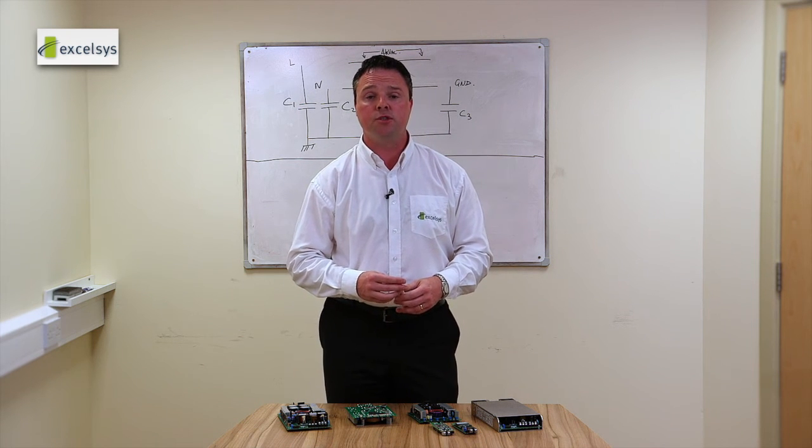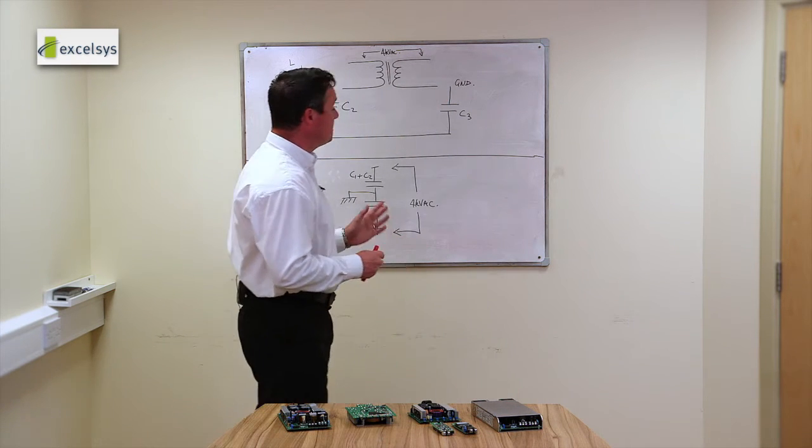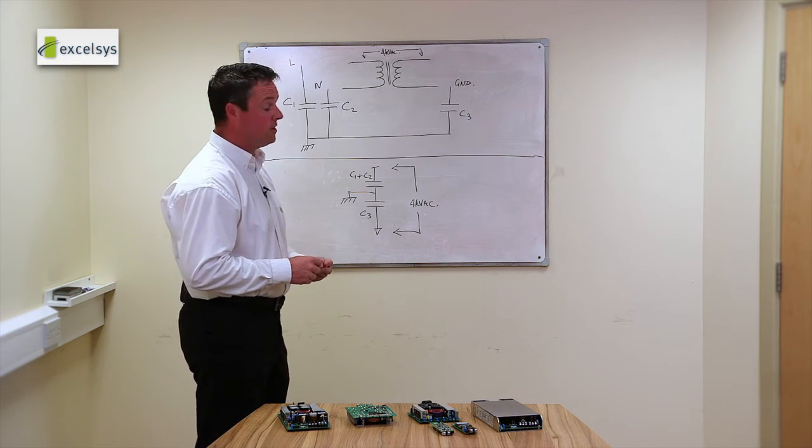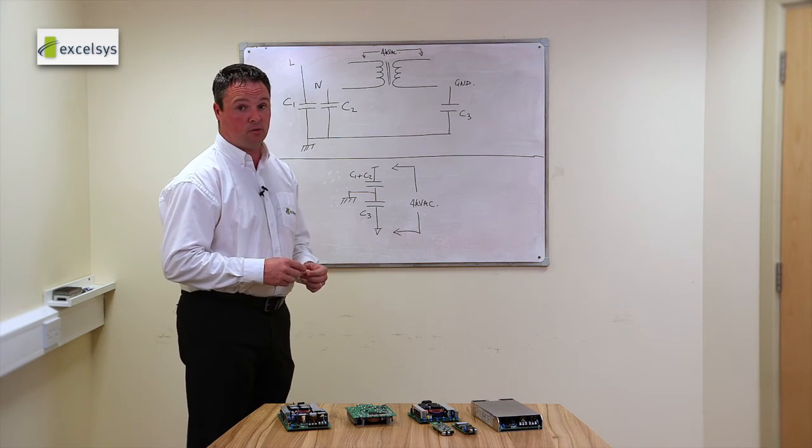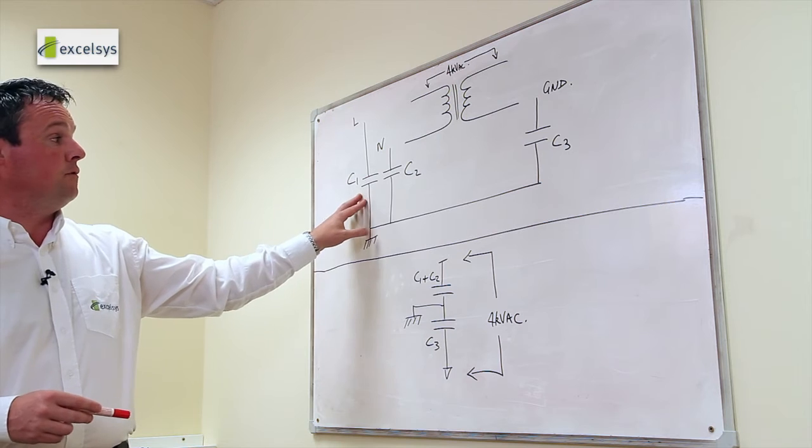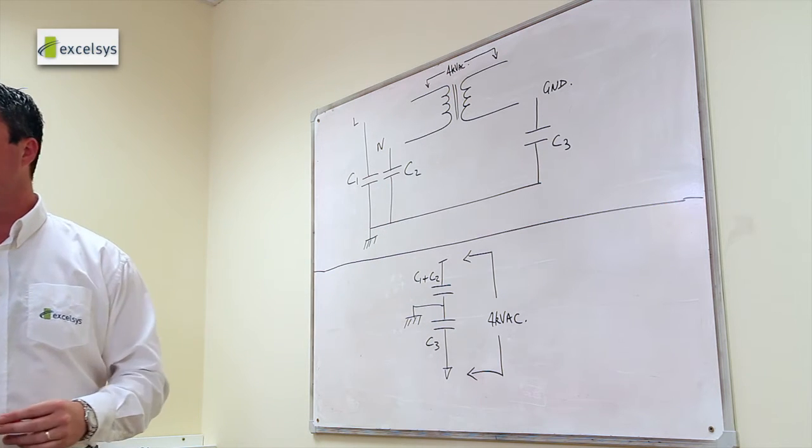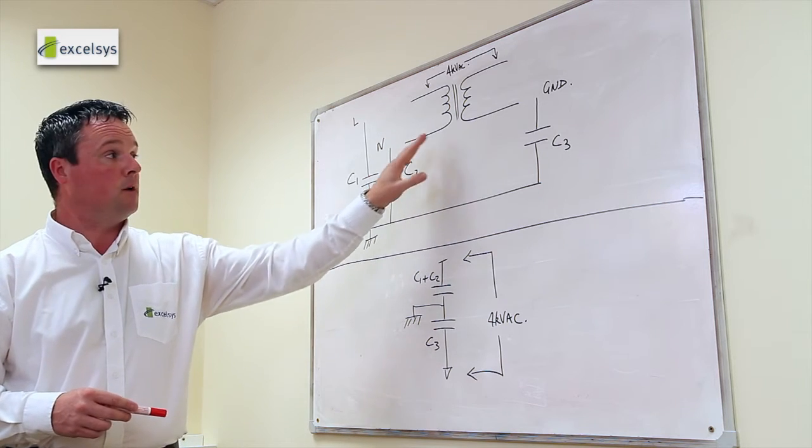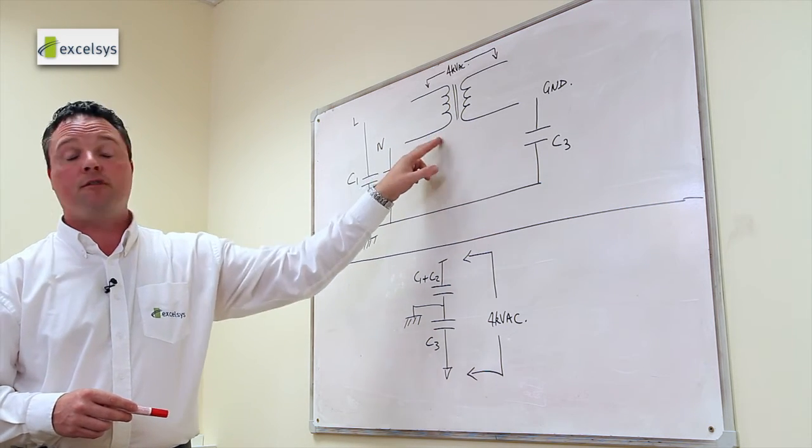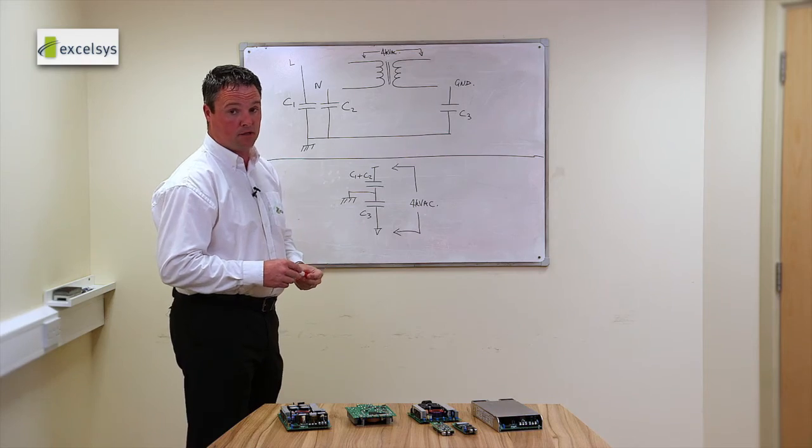So the solution to these are threefold. The first one is that because it is type testing, you were only testing for the dielectric breakdown. And under EN 60601 guidelines, you can remove these Y capacitors. So that's the first step. Remove the Y capacitors, complete the test and you're verifying that the dielectric of the isolation barrier doesn't break down.